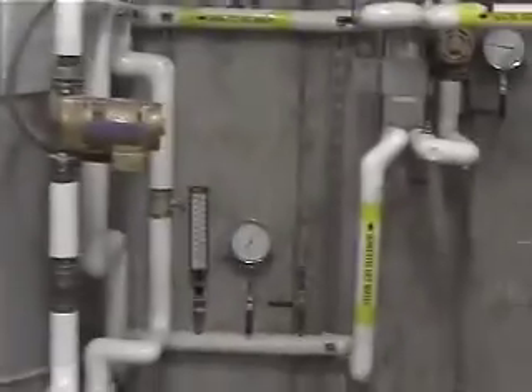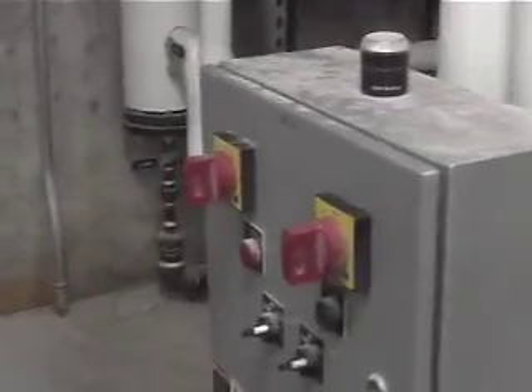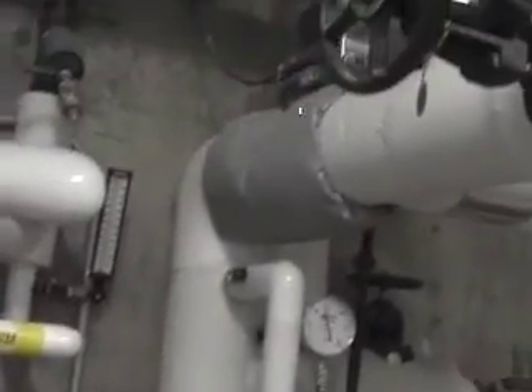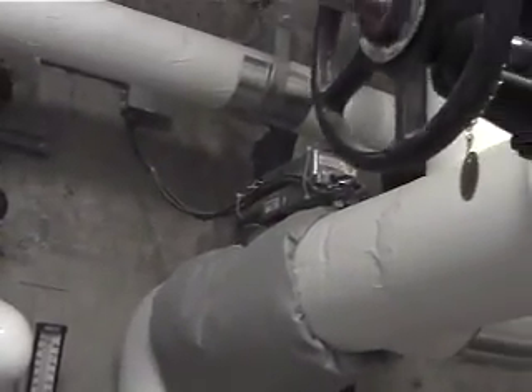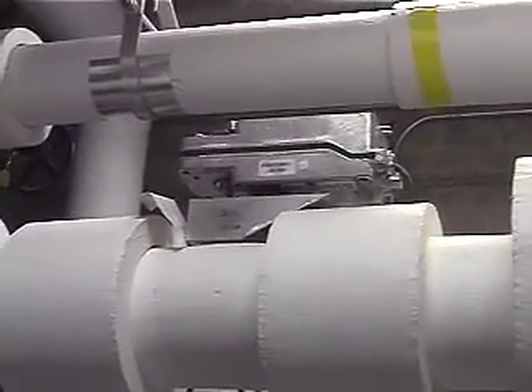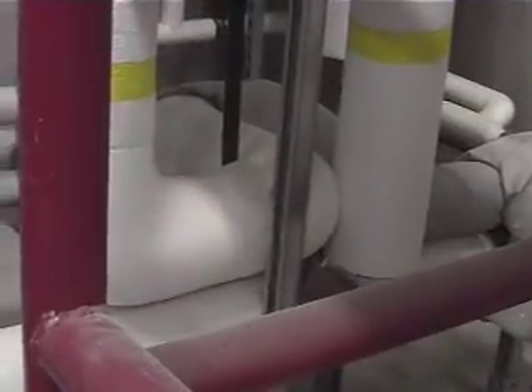So here's our PRVs. I think they're a 1-inch PRV. If we look at a PRV, of course it goes from a high inlet pressure to a low pressure. Here we're coming through an electric control valve over to two other electric control valves that supply the steam to the heat exchanger based on the outgoing temperature that's required. Off of the shell and tube heat exchanger, we come down here to two Armstrong F&T steam traps, thermostatic, that discharge into our condensate return system that returns the condensate.